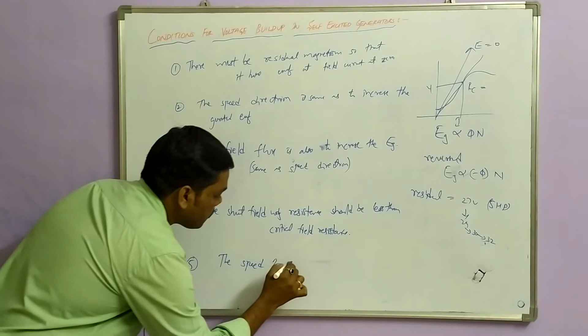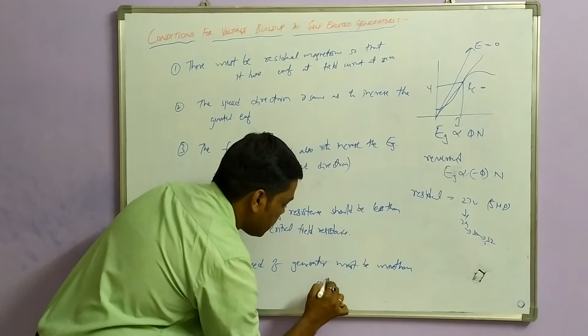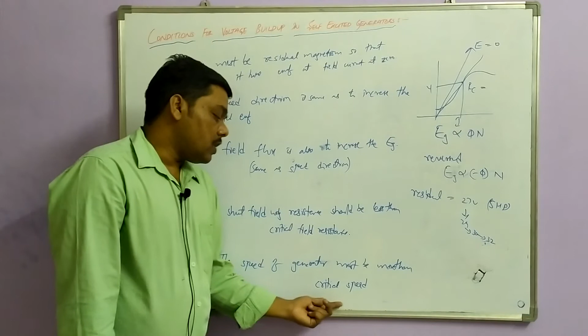Okay, next, the fifth point is the speed of the generator must be more than the critical speed. Now this is the maximum quantity, and this is a minimum speed. So you should maintain the minimum speed, which you can call the critical speed. If you go below this speed, the shunt generator may not run, it may not induce the EMF. So you should have the minimum value of speed. We already discussed that critical speed is where the shunt field winding resistance becomes the critical field resistance, the maximum value. The speed corresponding to that will be the critical speed.